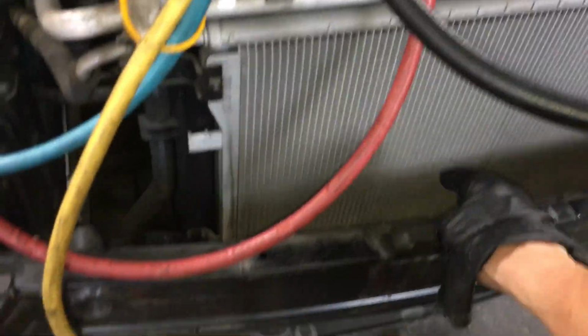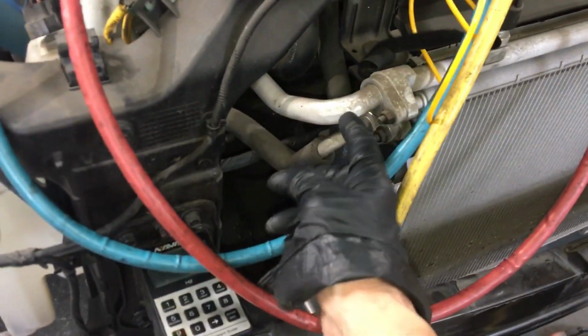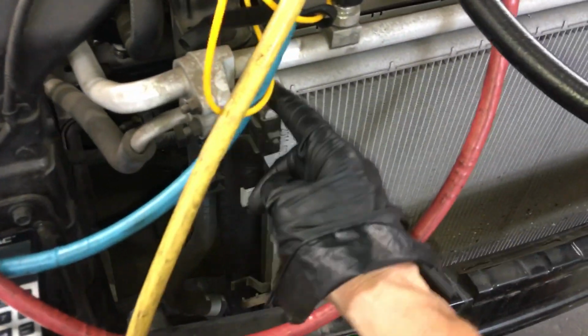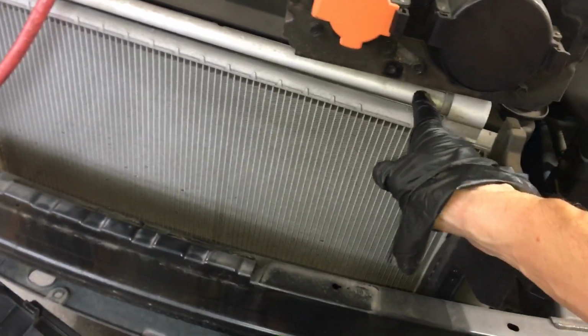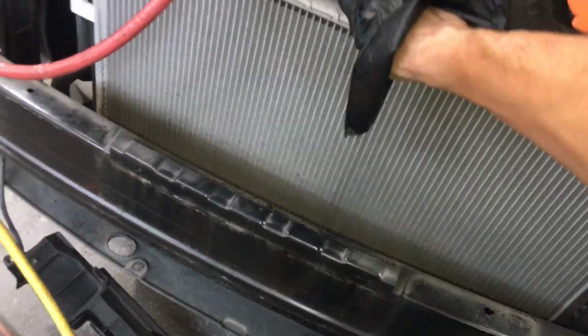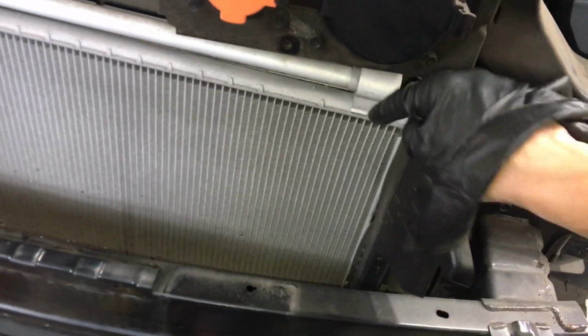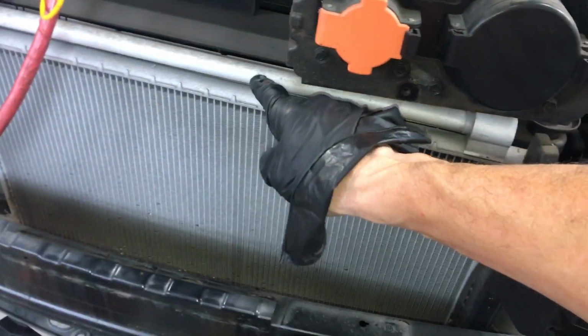So let's get back to this electric vehicle. The condenser flow is vertical, not horizontal. Our header is up here, check the header out, check the pipes out. Isn't this kind of unusual? Look at the size of that pipe for an automotive vehicle going back to the condenser. Why? Because that's like your evaporator, that's your suction line. Look at the size of that line coming from a condenser. Have you ever seen a condenser with a number 12 line on it?